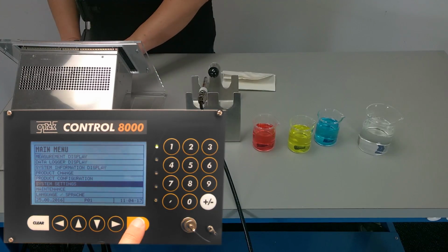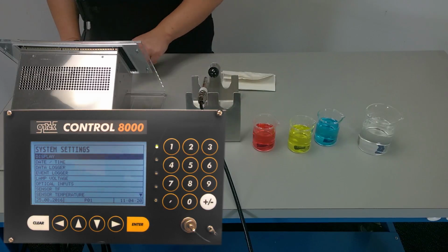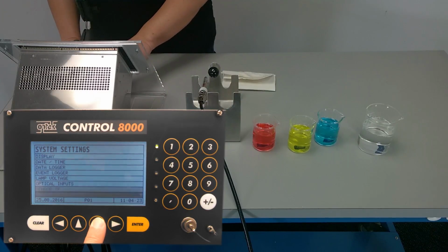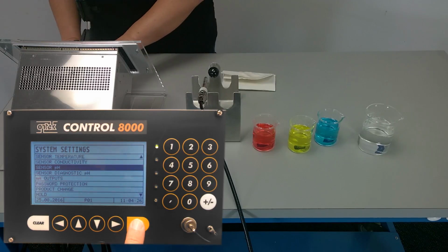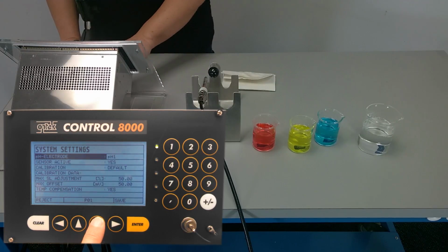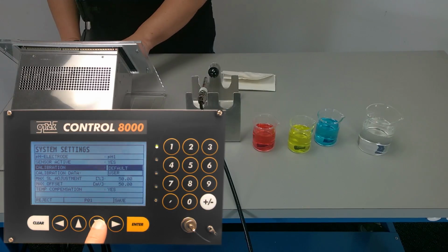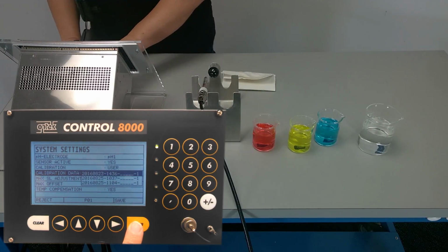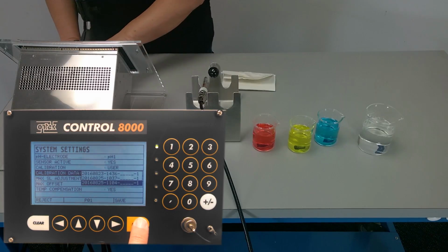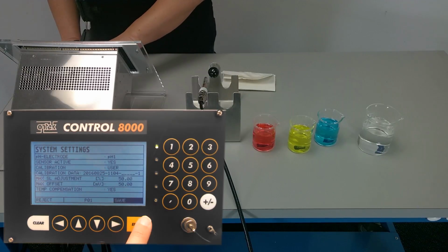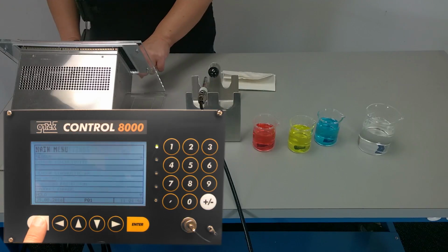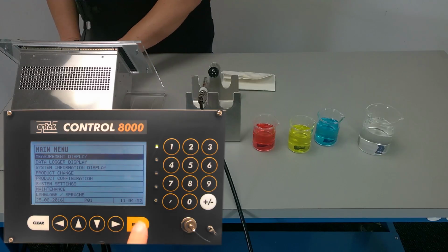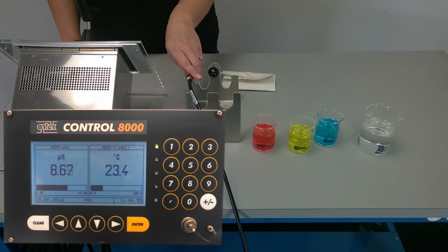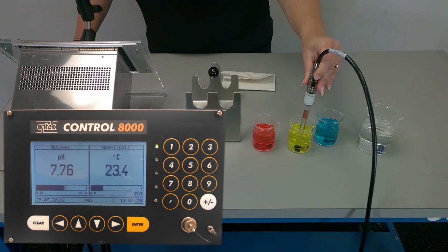And then we are going to go to System Settings, and we are going to select our sensor pH again. So we will scroll all the way through this first screen, keep scrolling, and then you will hit Sensor pH. And so from here, we will go to Calibration and select User. And now we will have a new calibration data set that will pop up. So we will select the date and time stamp code that is appropriate, scroll down to Save, and then from here, hit clear until you get to the main menu, hit clear again, and it will take you to the top of the menu. We are going to go to the measurement display and view our pH buffer 7 value.